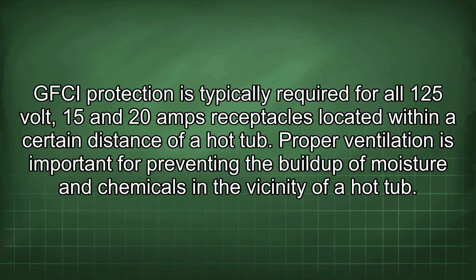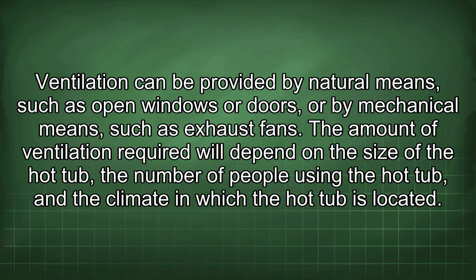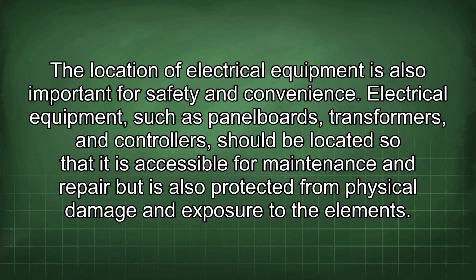Proper ventilation is important for preventing the buildup of moisture and chemicals in the vicinity of a hot tub. Ventilation can be provided by natural means such as open windows or doors, or by mechanical means such as exhaust fans. The amount of ventilation required will depend on the size of the hot tub, the number of people using the hot tub, and the climate in which the hot tub is located. The location of electrical equipment is also important for safety and convenience. Electrical equipment, such as panel boards, transformers, and controllers, should be located so that it is accessible for maintenance and repair but is also protected from physical damage and exposure to the elements.